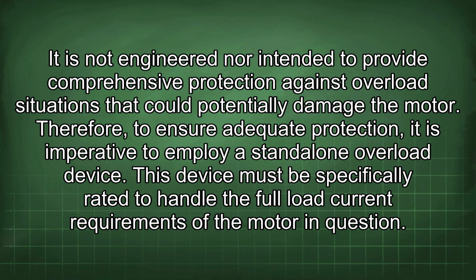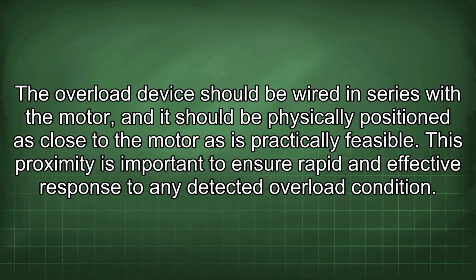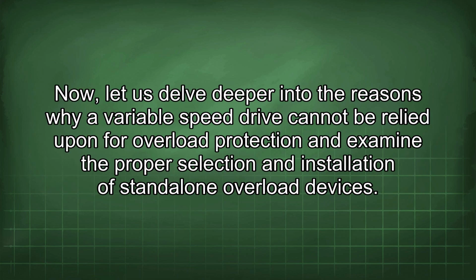This device must be specifically rated to handle the full load current requirements of the motor in question. The overload device should be wired in series with the motor, and it should be physically positioned as close to the motor as is practically feasible. This proximity is important to ensure rapid and effective response to any detected overload condition. Now, let us delve deeper into the reasons why a variable speed drive cannot be relied upon for overload protection and examine the proper selection and installation of standalone overload devices.